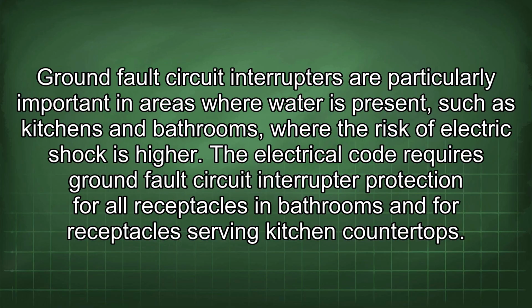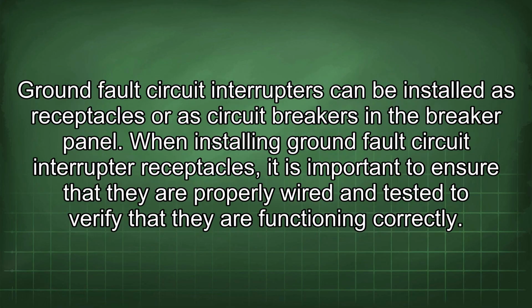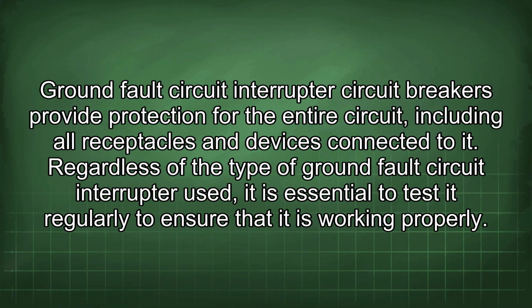The electrical code requires ground fault circuit interrupter protection for all receptacles in bathrooms and for receptacles serving kitchen countertops. Ground fault circuit interrupters can be installed as receptacles or as circuit breakers in the breaker panel. When installing ground fault circuit interrupter receptacles, it is important to ensure that they are properly wired and tested to verify that they are functioning correctly. Ground fault circuit interrupter circuit breakers provide protection for the entire circuit, including all receptacles and devices connected to it. Regardless of the type used, it is essential to test it regularly to ensure that it is working properly.